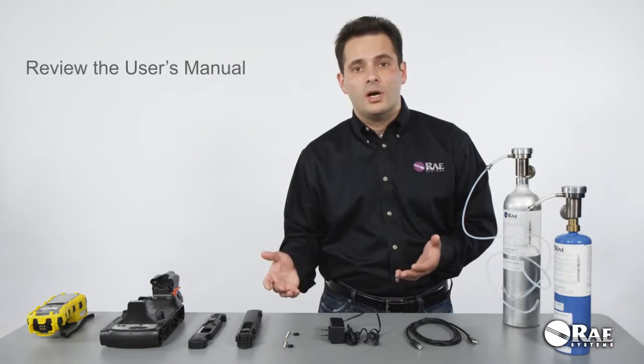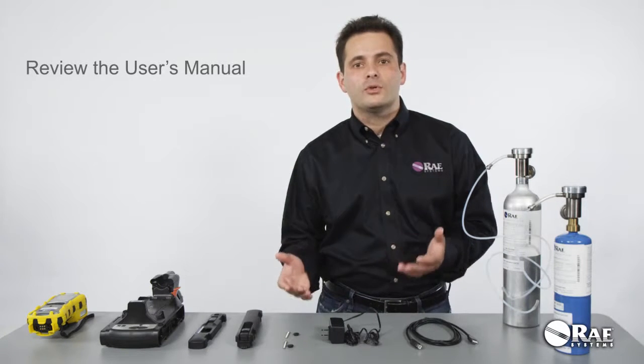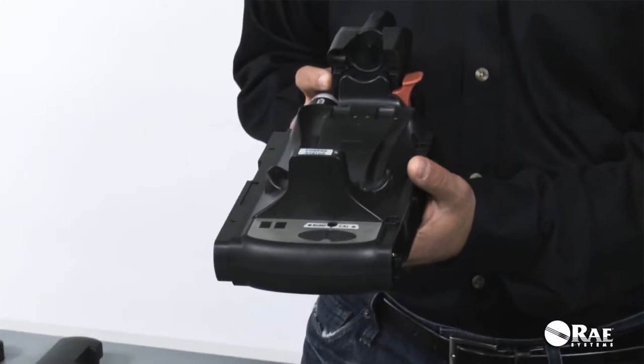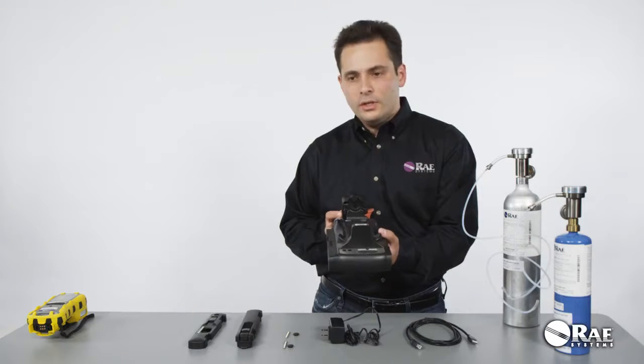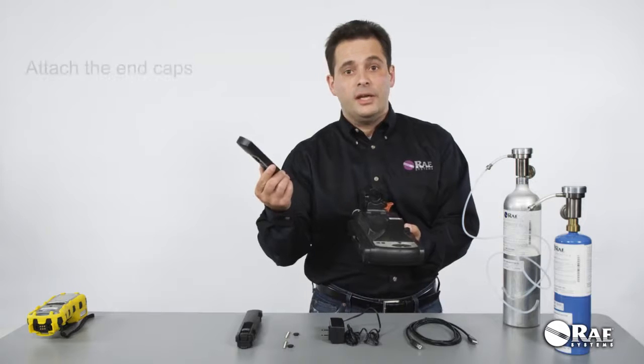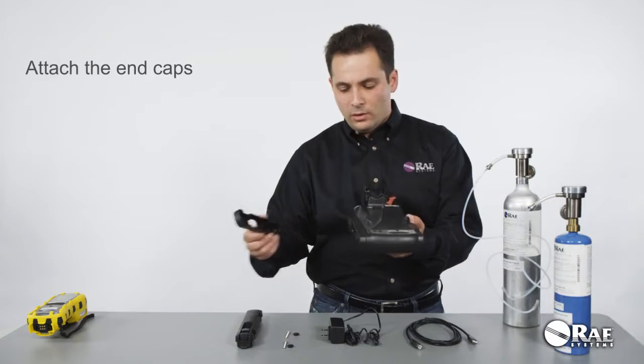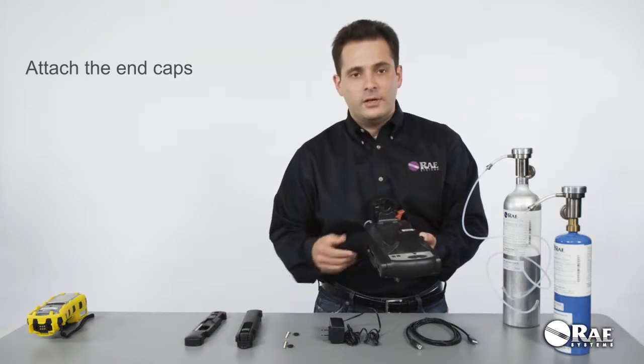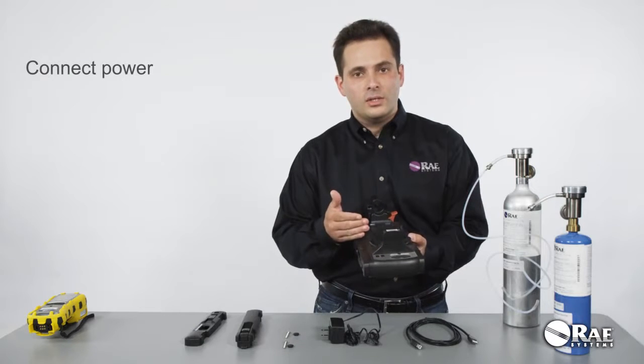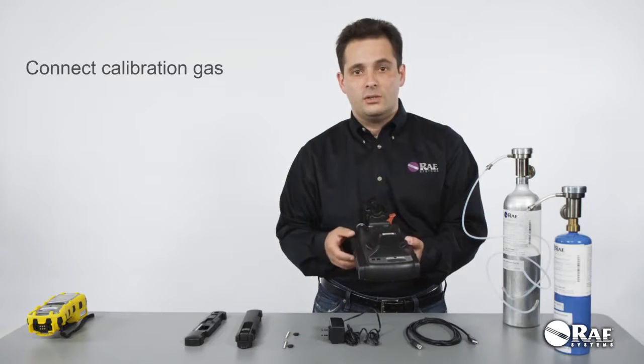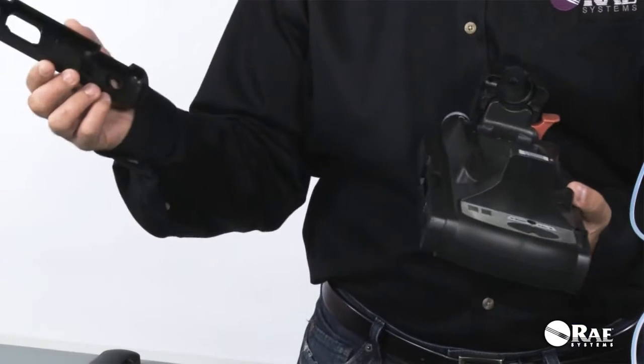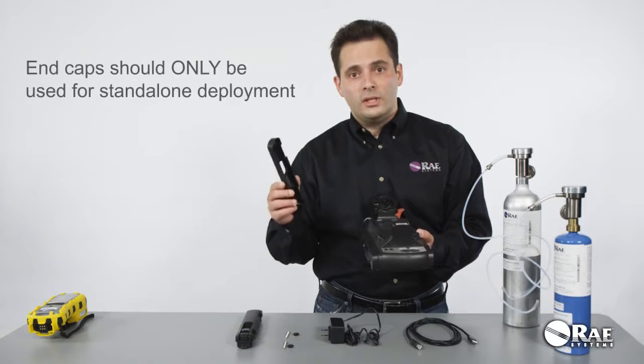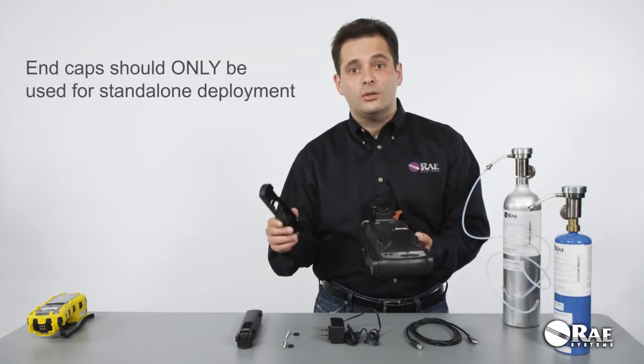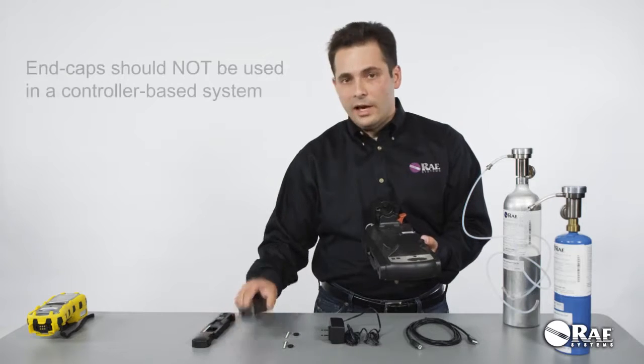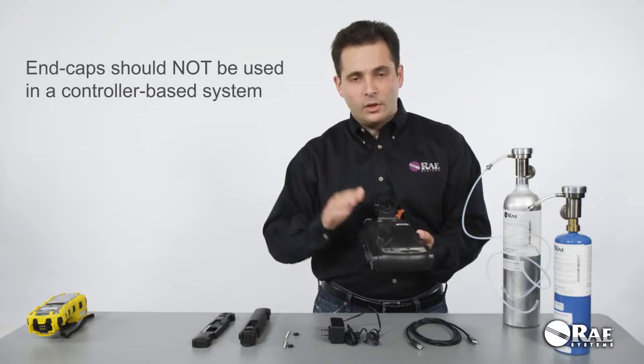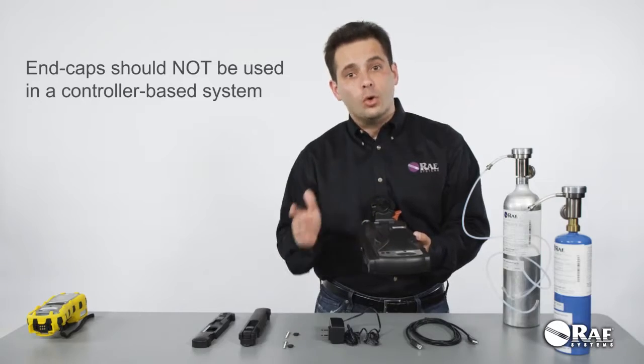Before you start the setup process, please make sure to review the user's manual. The setup process is very simple. All you need to do is to attach the end caps to the cradle, fix them with the screws, then power the system and connect calibration gas. It's that easy. There are two end caps that are used when the station is deployed in a standalone mode. These two end caps are not used when the cradle is deployed as part of a controller-based system.